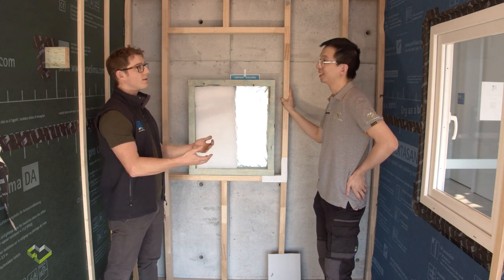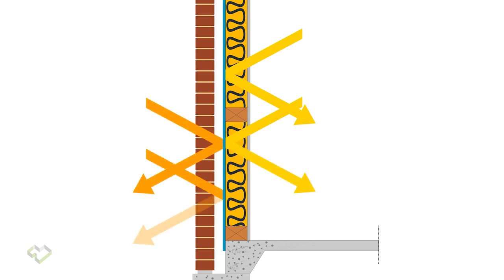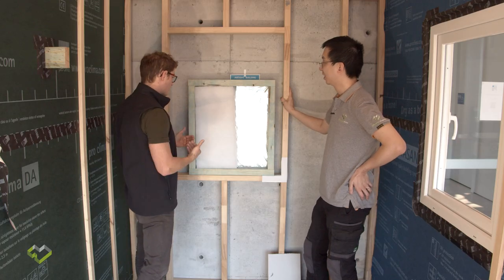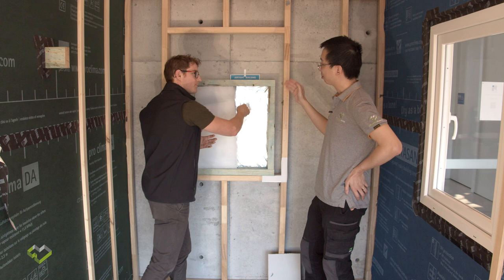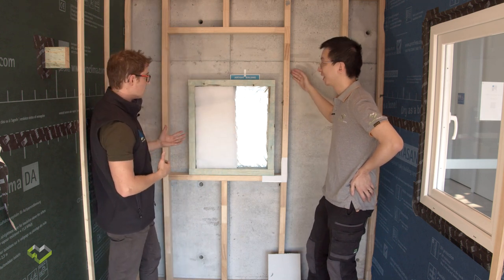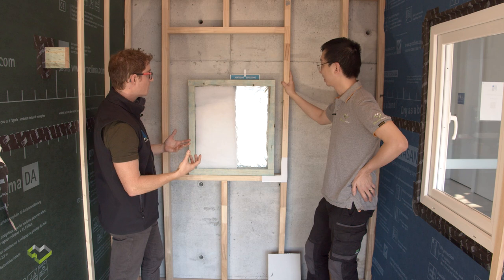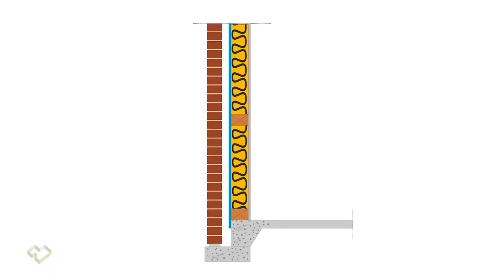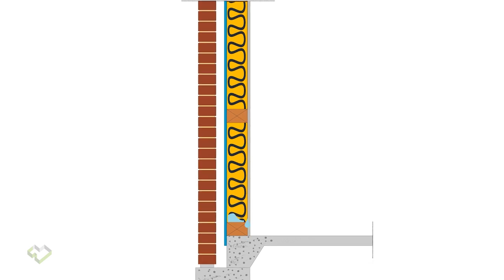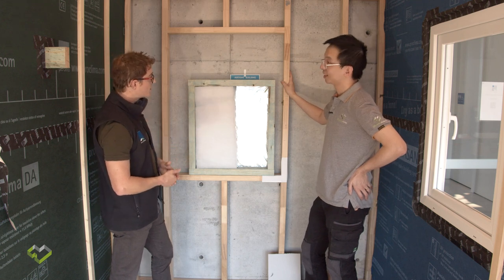Adding insulation is a good thing. We're adding more insulation to make buildings more energy efficient. What this does is — because the insulation is holding more heat back in the building, doing its job — it means the external surface is colder, it's closer to the outdoor temperature. So we've got a more energy-efficient building, but we start creating this plane that is nice and smooth, and because this foil is 100% non-porous, any elevation in humidity next to a cold surface causes condensation, like a beer glass.